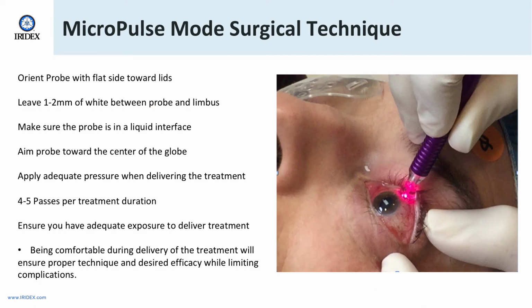The surgical technique for micropulse is a little bit different than continuous wave. The probe has an orientation with the flat side of the probe towards the lids. We want to leave about 1 to 2 millimeters of white between the probe and the limbus. We want to make sure that the probe is in a liquid interface of at least BSS or gonioscopy gel. We want to be aiming the probe towards the center of the globe.